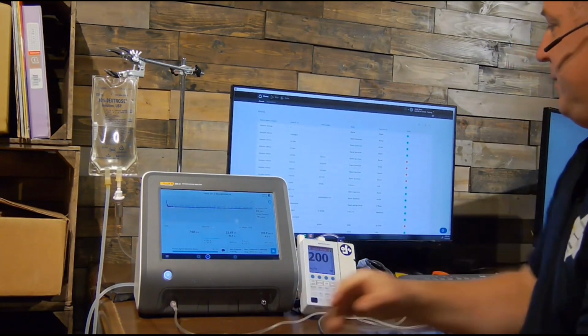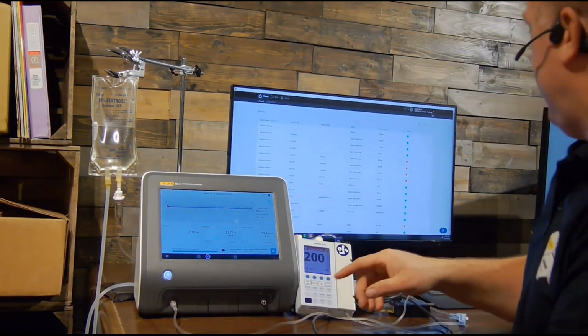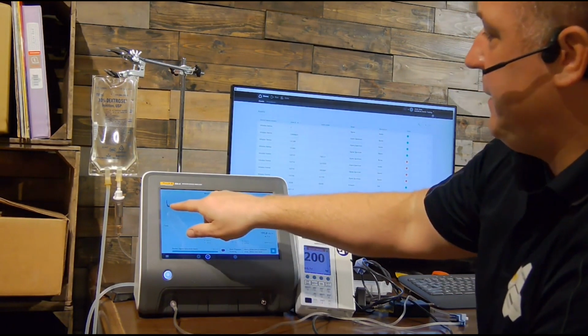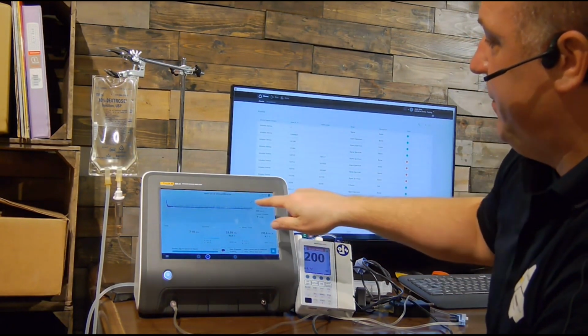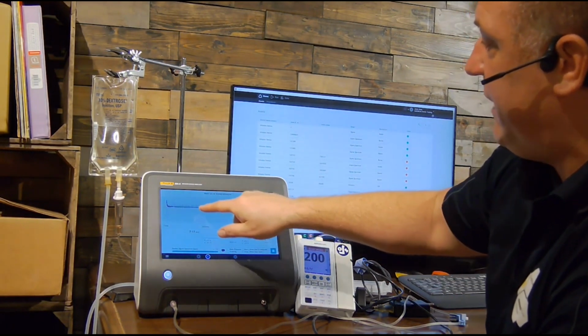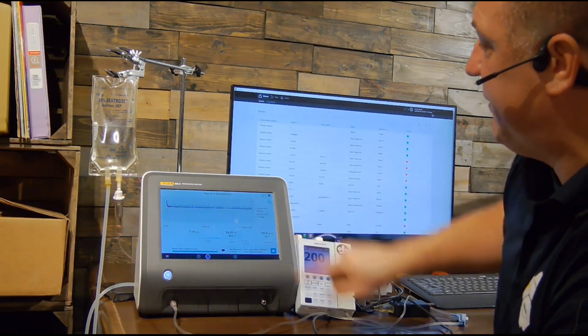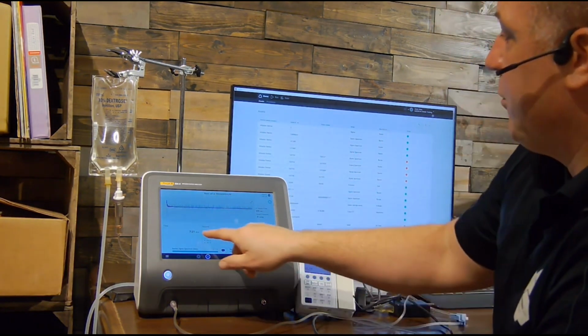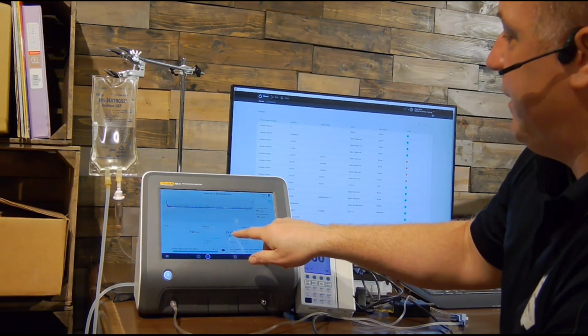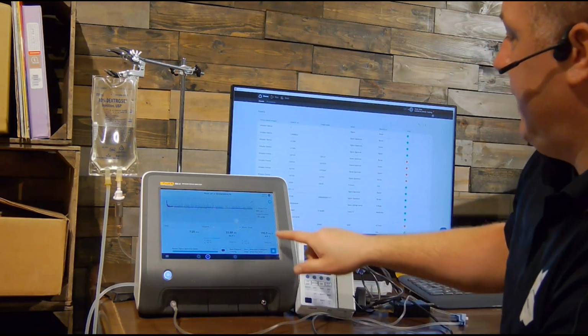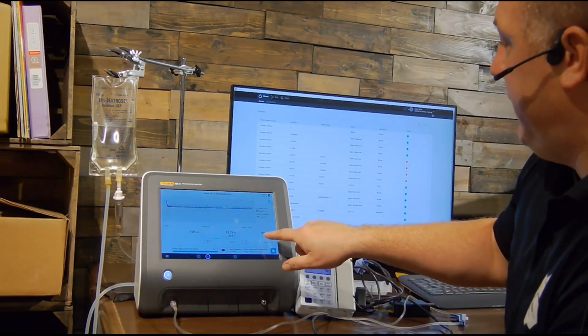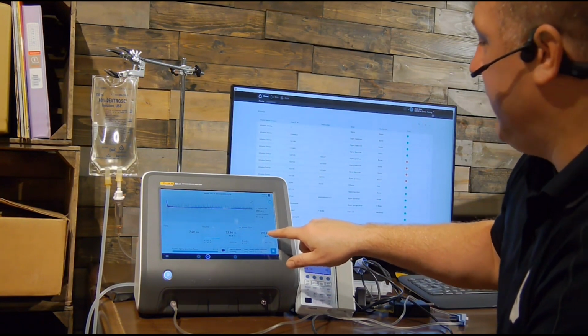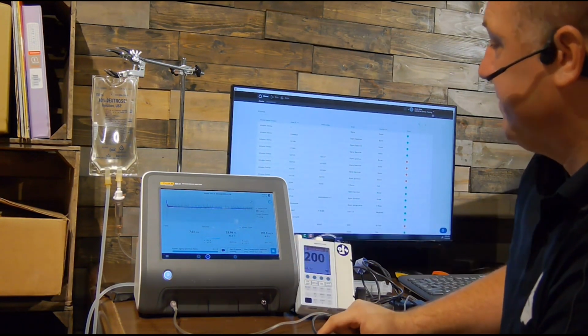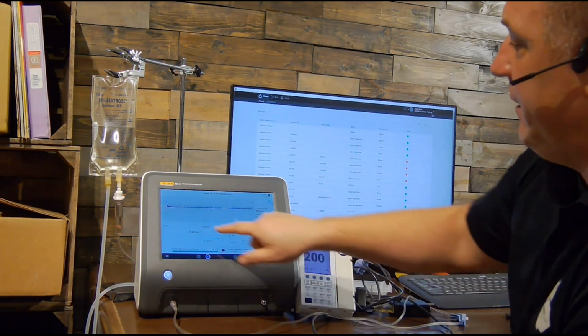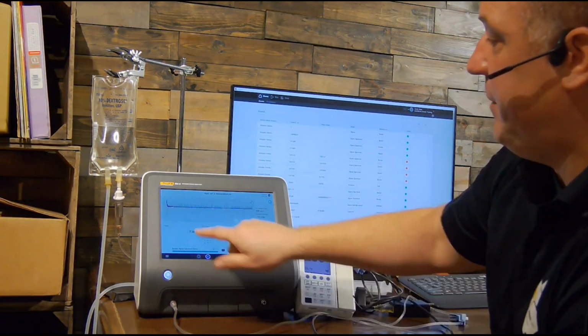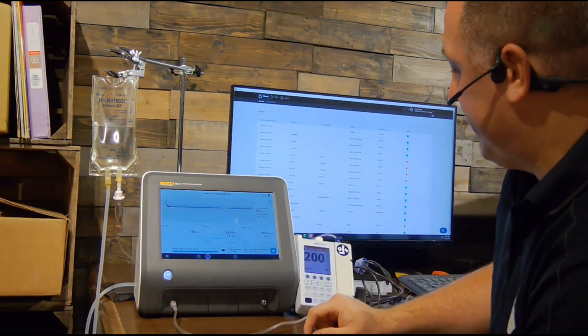All right, let's check back in on our IV pump here real quick. Let's see where we're at. Right here we see our average flow in purple, and our instant flow in blue. You can see each time one of those peristaltic fingers resets. Right now we've pushed so far 23.47 milliliters, and our mean flow is 190.6 milliliters an hour. You can see your tolerances in it. The total test time so far has been 7 minutes and 36 seconds.